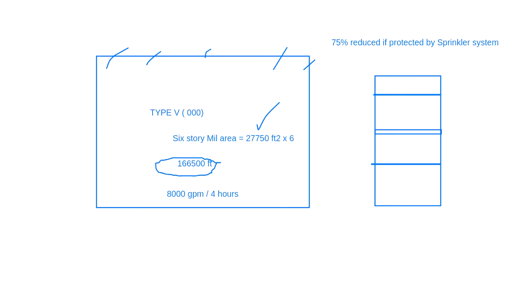So we have a requirement of around 2,000 GPM water for these factories, right? So the minimum number of hydrants for this one should be two. We have to place two hydrants around these areas, and the maximum spacing between the hydrants should not be more than 152 meters or 500 feet. Now, what is the spacing between those hydrants, and what is the flow requirement, right?